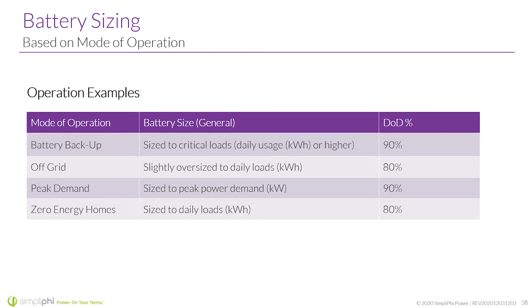I won't harp on this too much since I just said it, but again, using the standard, batteries should be sized to twice the inverter's output capability. So if it's an 8 kilowatt inverter like this one, we need a minimum of 16 kilowatt hours of battery. I can't stress that enough. I've seen people say, well my customer's only going to use 4,000 watts continuous, put 2 batteries on an 8,000 watt Radian, and then the customer starts adding loads when they're gone and they fry their battery - and it's not covered.